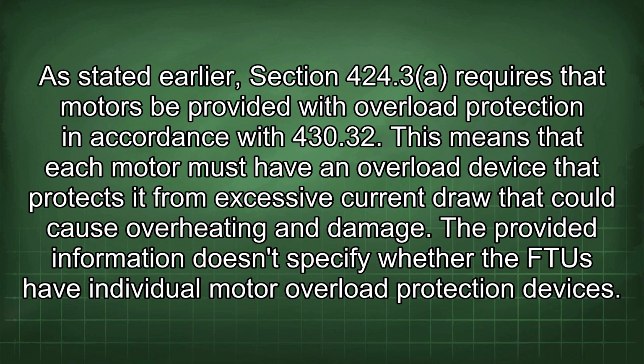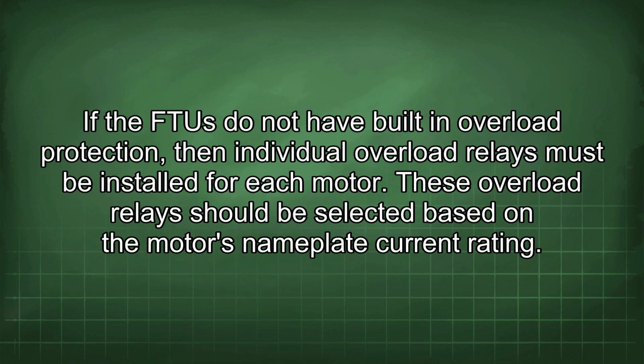430.32. This means that each motor must have an overload device that protects it from excessive current draw that could cause overheating and damage. The provided information doesn't specify whether the FTUs have individual motor overload protection devices. If the FTUs do not have built-in overload protection, then individual overload relays must be installed for each motor. These overload relays should be selected based on the motor's nameplate current rating.